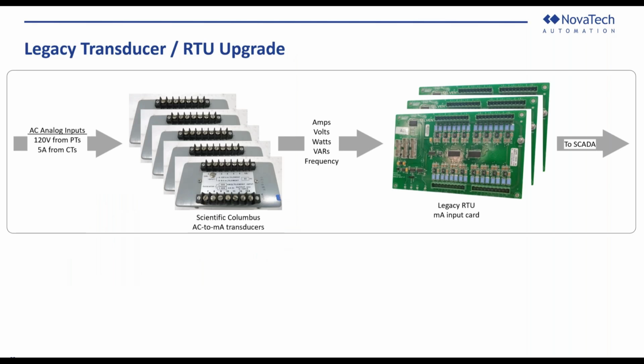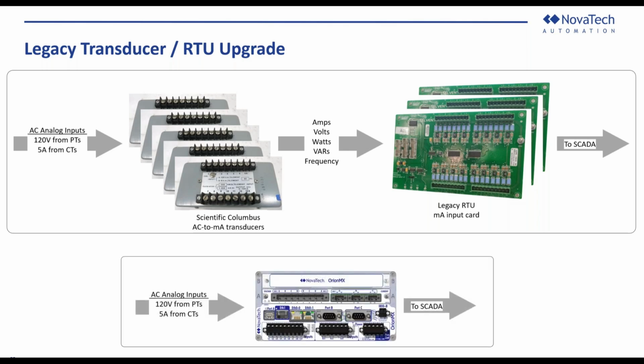Here's a legacy transducer. You've probably seen some of these old Scientific Columbus AC to milliamp transducers. They're still out there, fewer than there were, but you know how they work. 120 volt or 5 amp nominally from PTs and CTs being converted down to milliamp quantities, and then those milliamp quantities are input to a legacy RTU, which in turn goes to SCADA. You see something like this, you could alternatively go with a much simpler solution that looks like that. That solution below would be able to do what many of the legacy solutions like the above would be able to do.